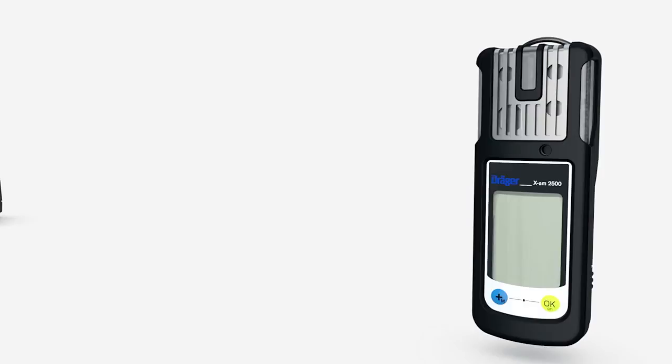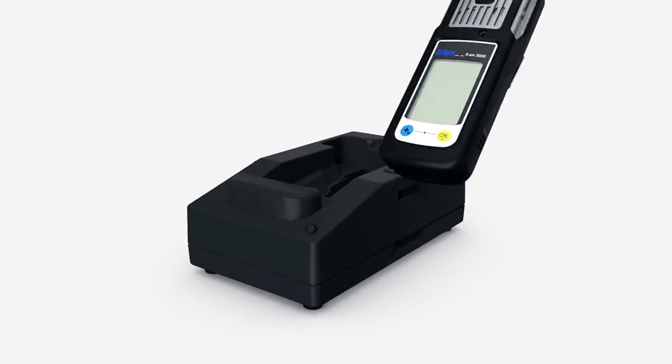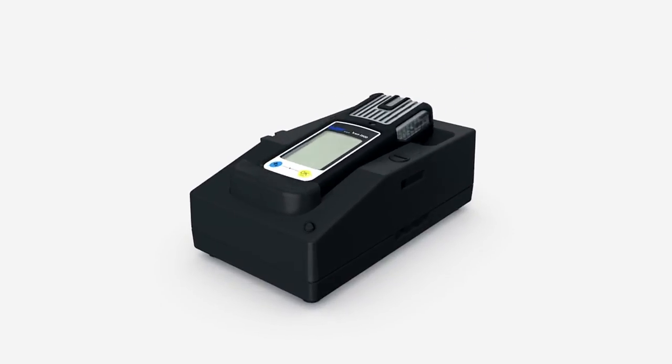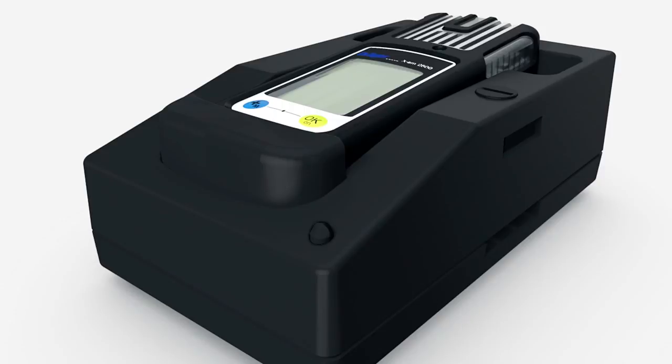If you use your Dräger X-am 2500 with rechargeable batteries, recharge it in the charger, which can also be used in a vehicle using the vehicle charger mounting kit. Place the instrument inside the charger. If the red LED is flashing, the device is still charging. If the light is on continuously, the device is fully charged.